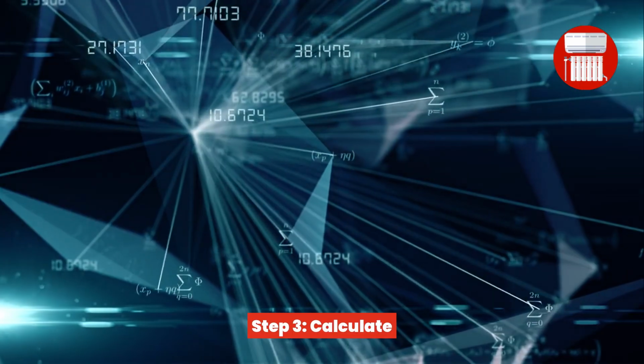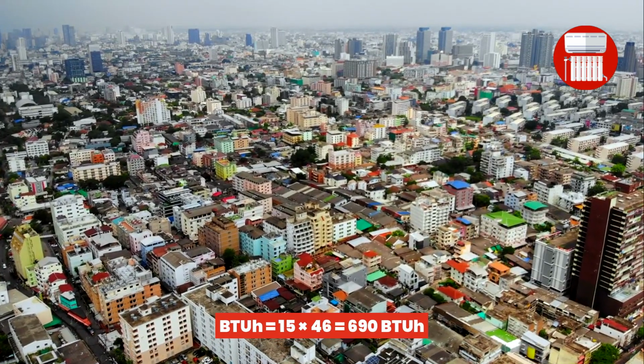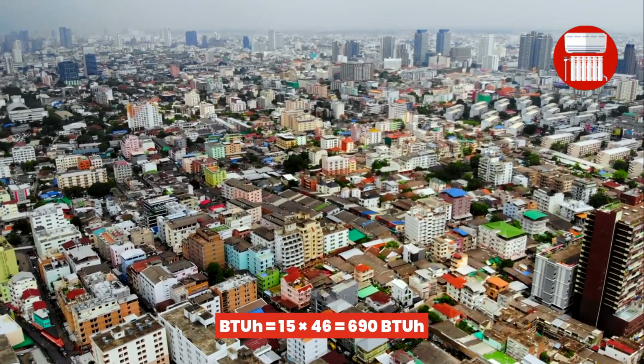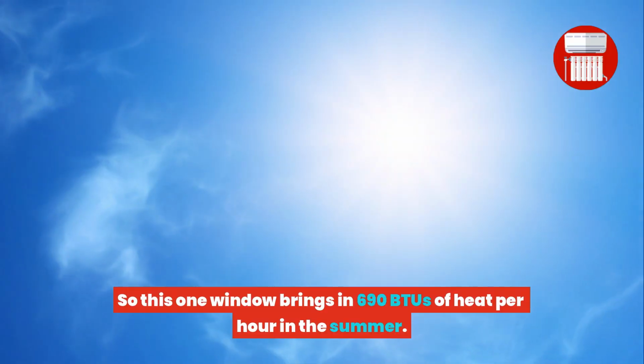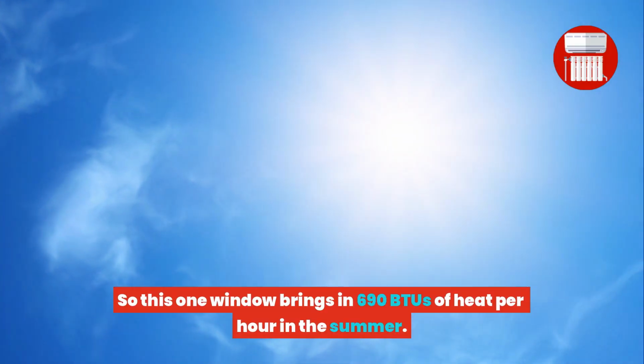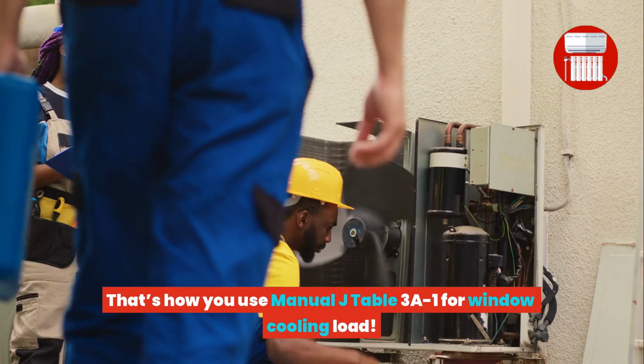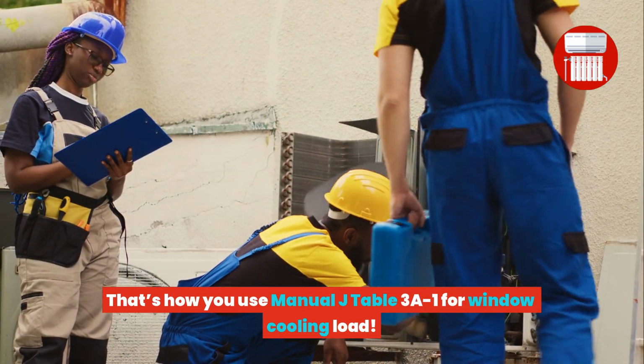Step 3. Calculate BTUH = 15 times 46 = 690 BTUH, so this one window brings in 690 BTUs of heat per hour in the summer. That's how you use Manual J Table 3A-1 for window cooling load.